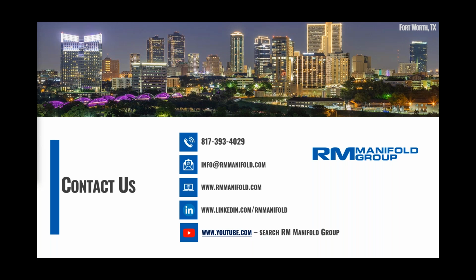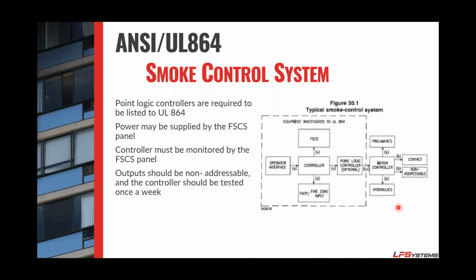Now, if you're using a BMS contractor, again, they should get the proper listings for the system. If you read the letter of the law per that diagram, which is this one here, that would actually fall into this category because it's not making decisions, it's just giving information. So technically the sensor doesn't have to be listed, but whatever it is driving does.